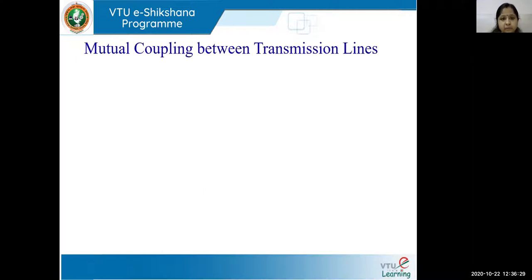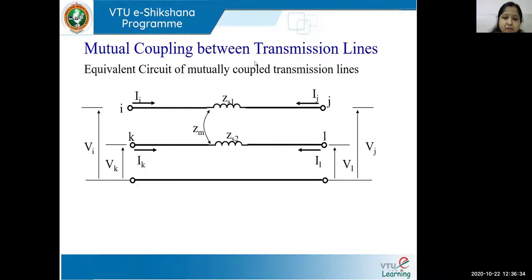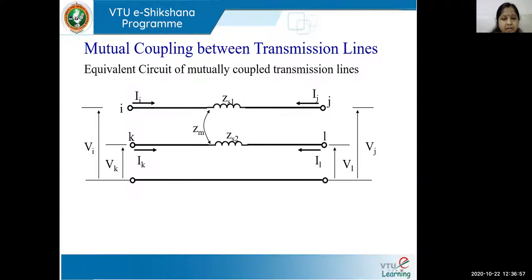Before we start, we need to understand what mutual coupling between transmission lines means. I'm explaining this concept with the help of two transmission lines. Once transmission lines get energized, they generate their own self magnetic field. That magnetic field gets affected by nearby or parallel lines' magnetic fields. Hence we say the two lines are mutually coupled, and this results in induced zero sequence voltage and current in both lines.